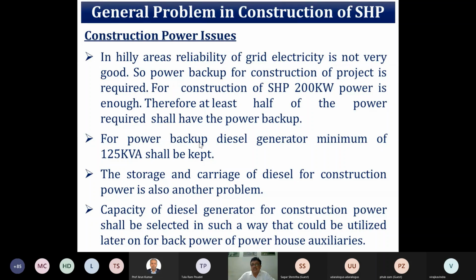In hilly areas, reliability of grid electricity is not very good, so power backup for construction power is required. Normally for a small SHP up to 25 megawatt, we require 200 kilowatt of construction power, and half of it should be the power backup. So a minimum of 125 KVA diesel generator shall be installed.